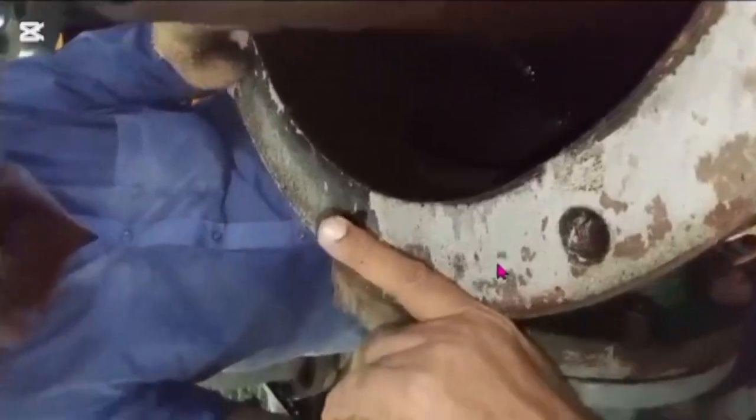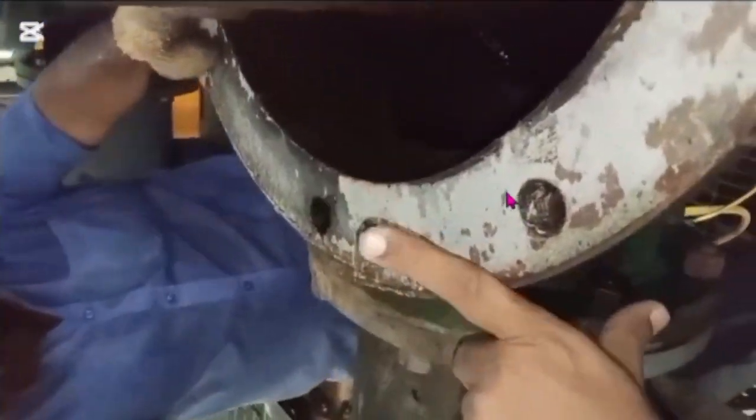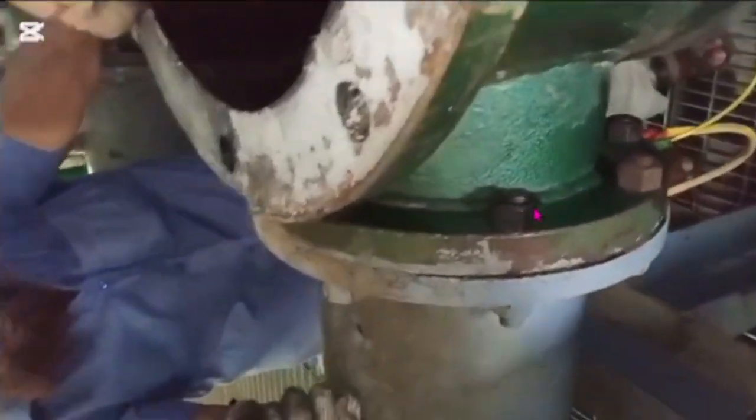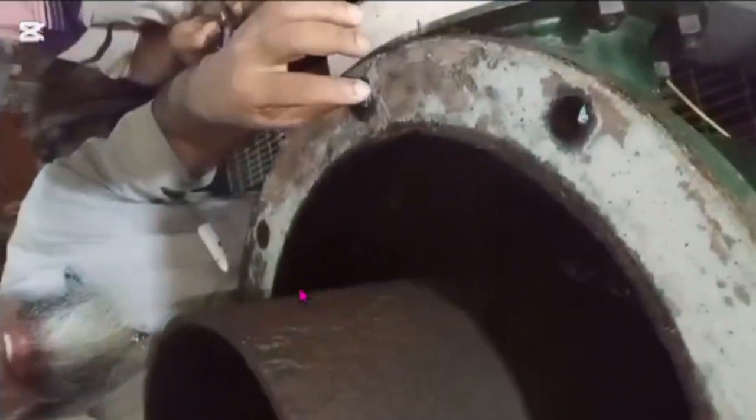Here at the ejector, we opened the upper cover and observed the pipelines inside the ejector, and we also followed how the ejector works. This is the inner side, and on this inner side we found iron particles. You see, this is the inlet of the water flow line.